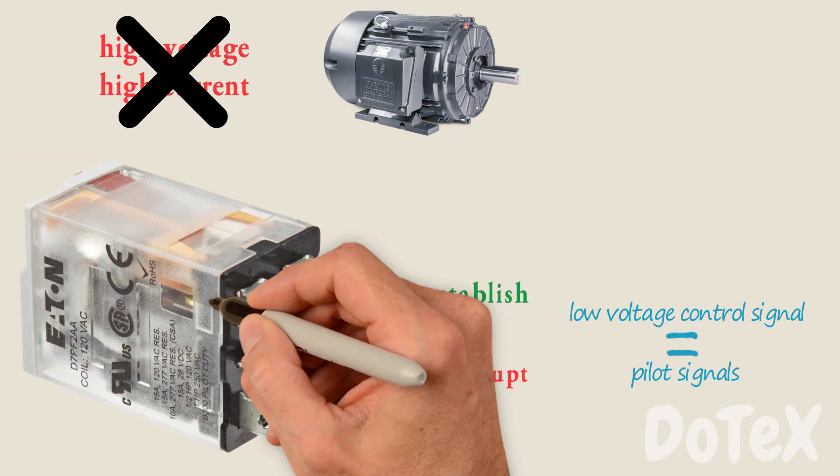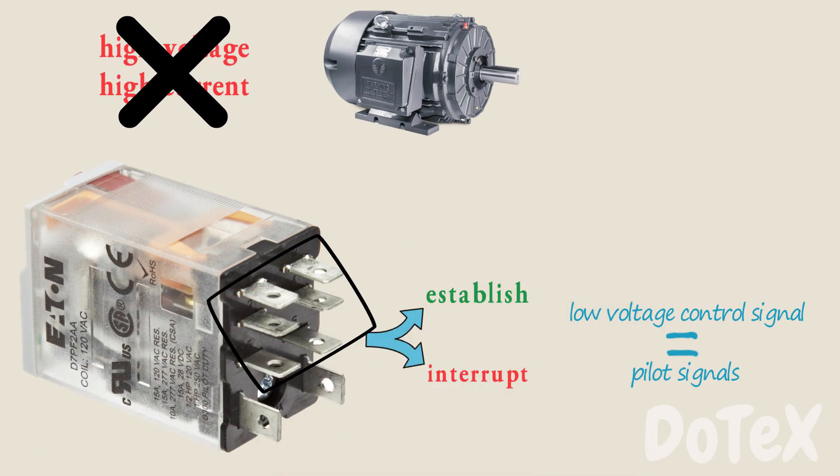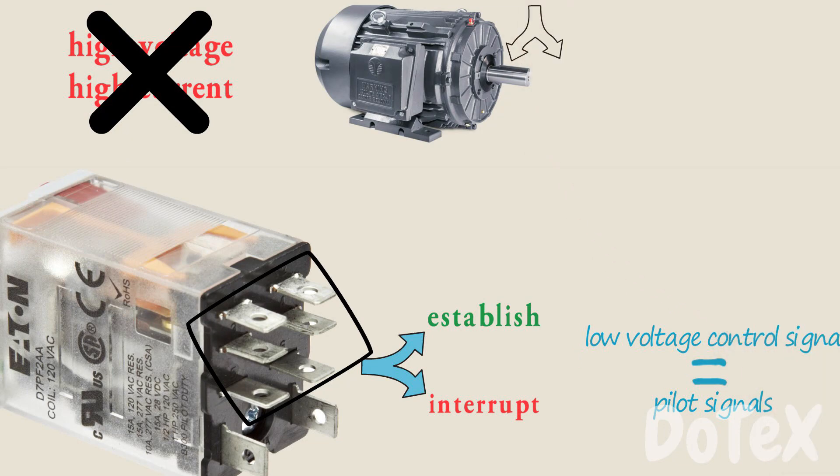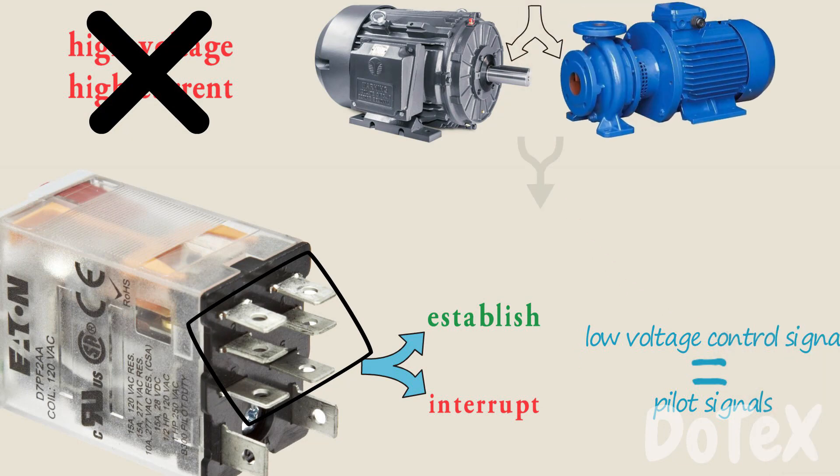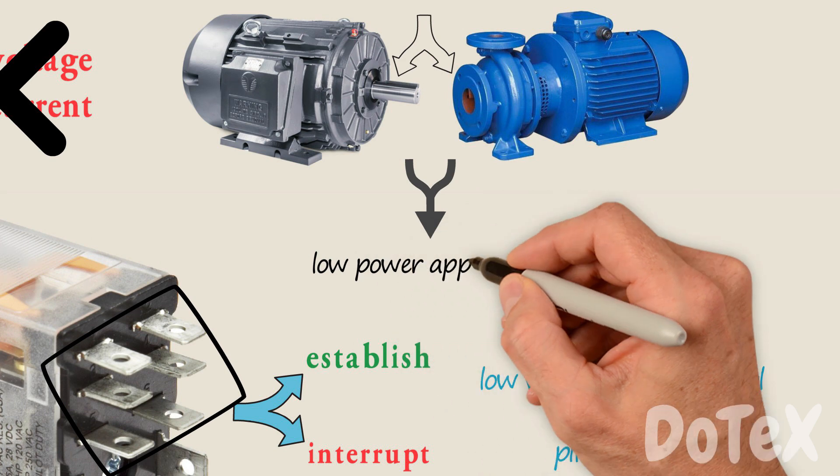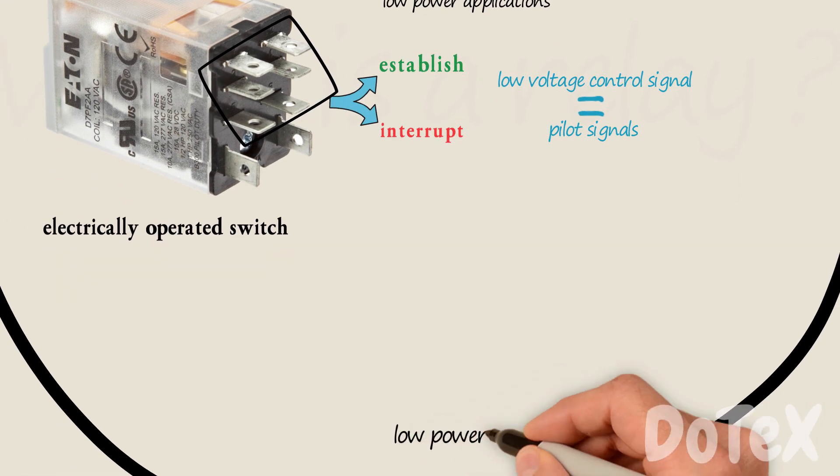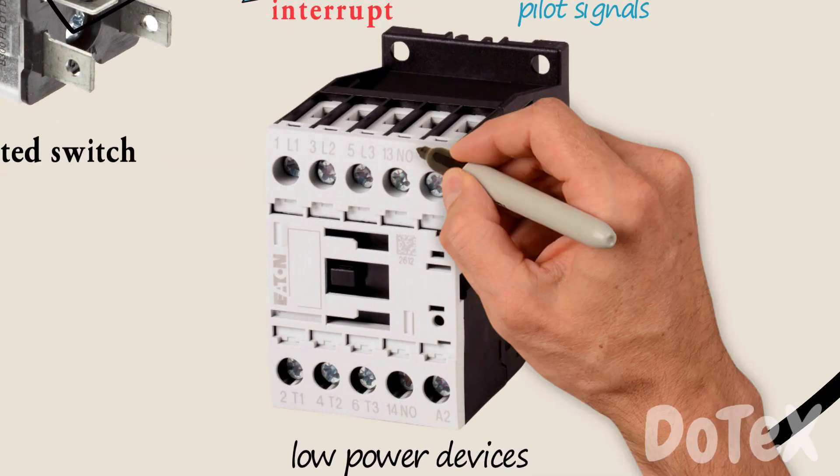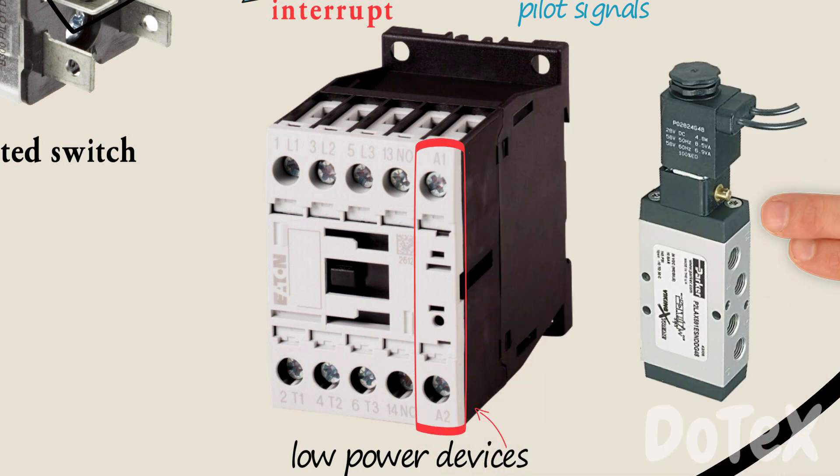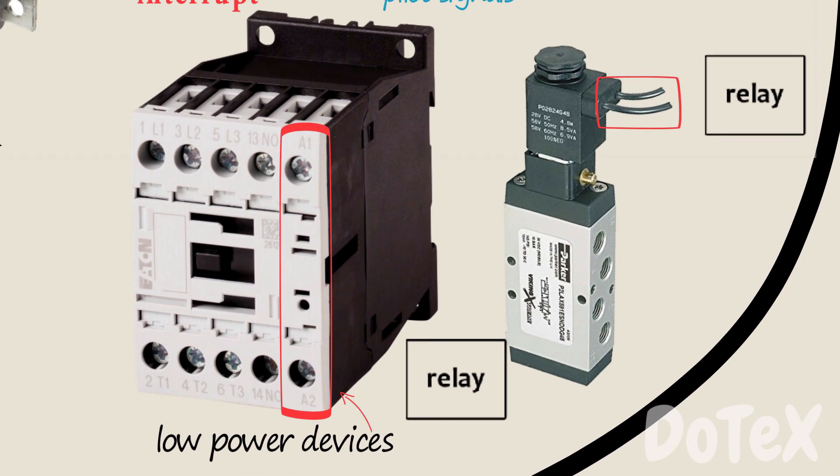Relay contacts rarely switch loads directly like motors or pumps and only do this in low power applications. Relays usually switch control signals, in other words low power signals, to other low power devices like the coils of contactors or the solenoids of hydraulic valves. Devices like contactors or solenoids, when ordered to work by the control signal, make the connection of heavy electrical or hydraulic power load.